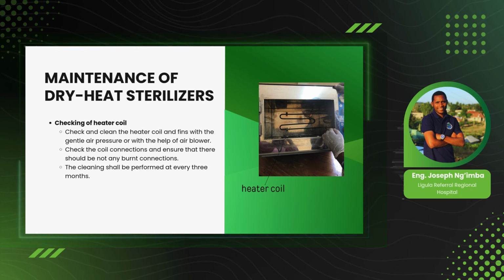The other thing we check during maintenance is the heat coil. The heater is the core of the machine to produce heat, to produce temperature. So we check the heater for any damage, and for any loose connection between the power cable and the heater. We also check if there is any ash or dust on the surface of the heater.